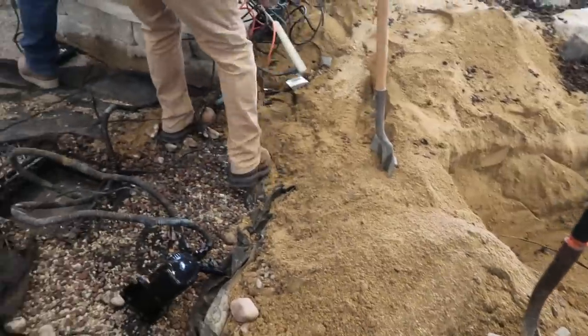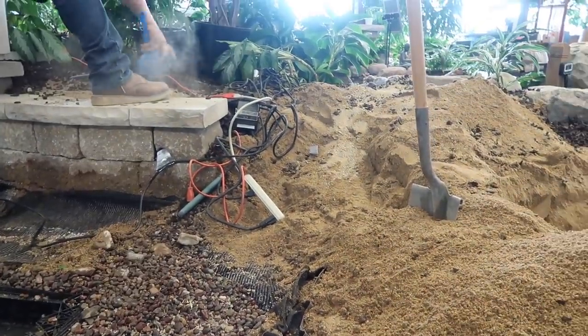We did find the source of the leak. So our leak was around the spillway bowls. Our liner stops here, and when the guys installed it, we had a bib liner going back underneath, or I guess that top spillway bowl. And what was happening is the two bowls were touching. Water was traveling back down the face of that bowl, hitting that bib liner, and then migrating this way.